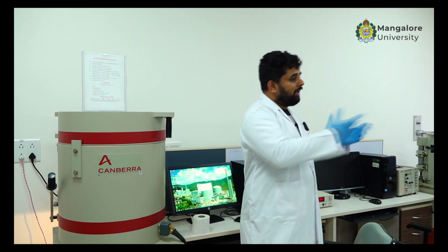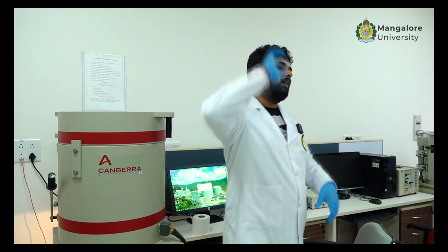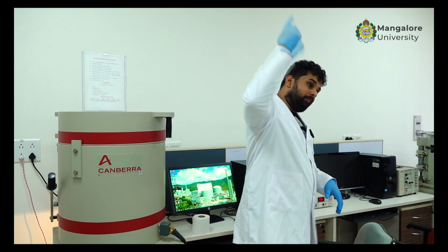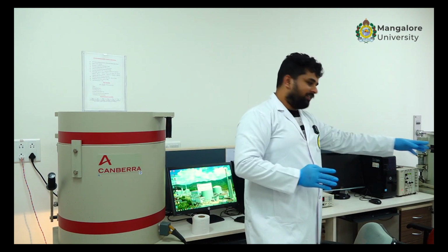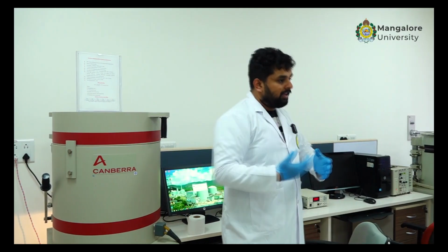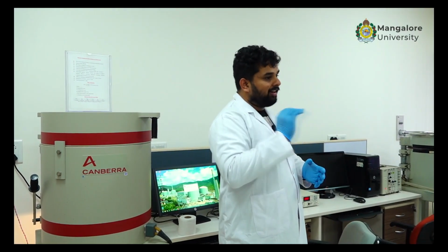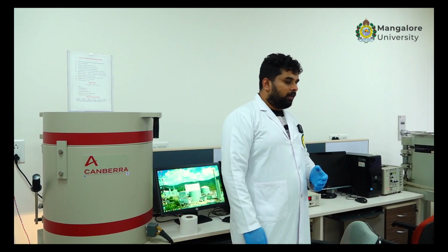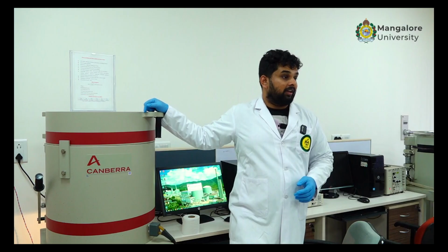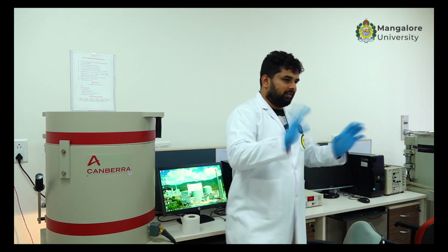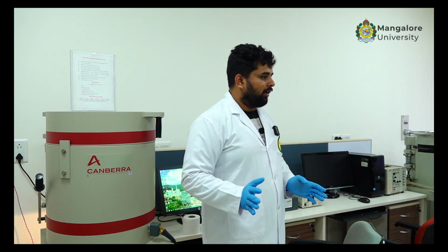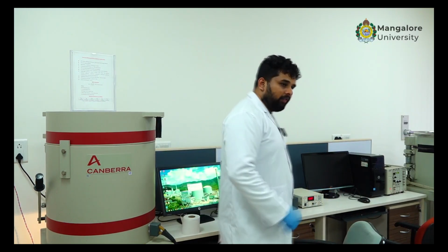I am not going to explain in detail. If you have doubts, you can ask later. So we seal it and keep it in the lab. There also one round of washing will go through, and when it comes here, it will already be clean. Still we clean it and keep it inside, so that it is cleaned 3 or 4 times thoroughly and the bottle doesn't contain any kind of dust particles. Because once a small amount of dust goes inside, it is very difficult to reduce the MDA. So this is the basic laboratory cleanliness and laboratory routine that we have to follow. Now the high voltage is set.